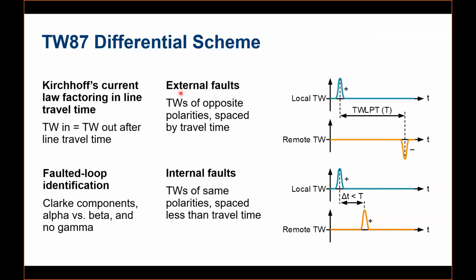So we can just consider a fault that is an external fault, that is not in the line. So we can just consider a traveling wave that's entering your local end with one of the polarities, say positive polarity. And once it travels along the line, it will reach the remote end as well. And the remote end will see it in a negative direction because of the CT polarity. So this is just like the current entering over here and the current leaving from the remote end. So the traveling waves recorded at both ends have opposite polarities. It's positive on the local end and negative on the remote end.